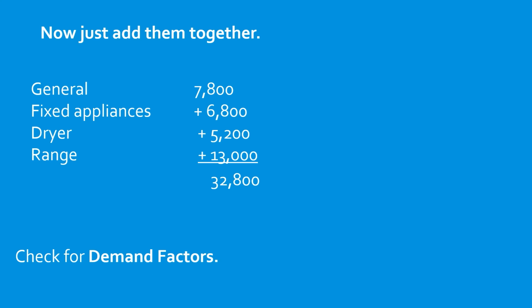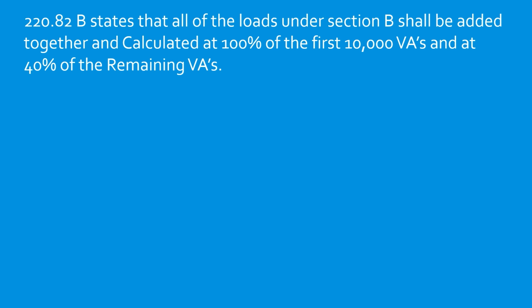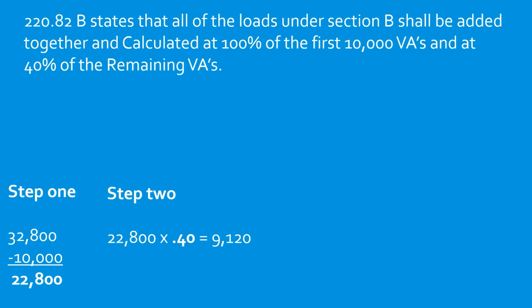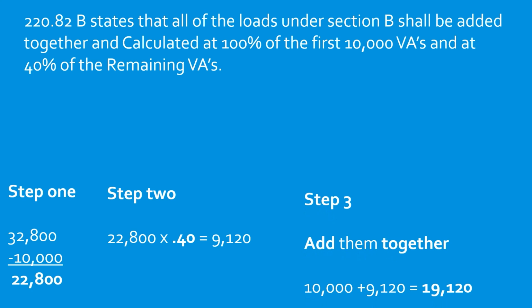Now we check for demand factors. And in 220.82(B), it states that we should calculate the first 10,000 at 100% and then 40% of the remaining VAs. Step 1, take your total minus 10,000. That's going to give you 22,800. Step 2, you're going to multiply that by the 40% demand factor, which is 0.40. That is going to give you 9,120. Then simply add them back together. 19,120 VAs for the general circuits of this home.